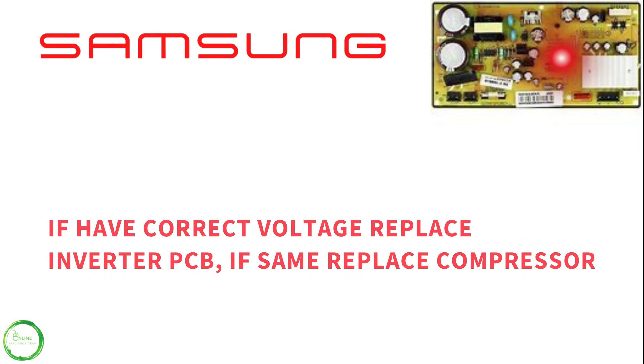If the voltage is correct, you would want to replace the PCB inverter, and if that does not fix the problem, replace the compressor.